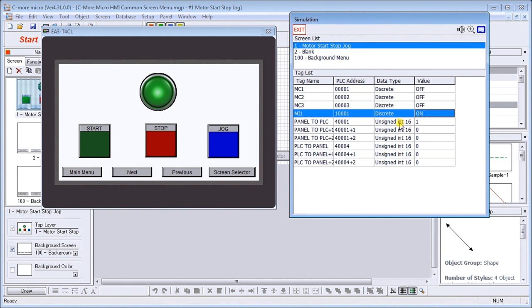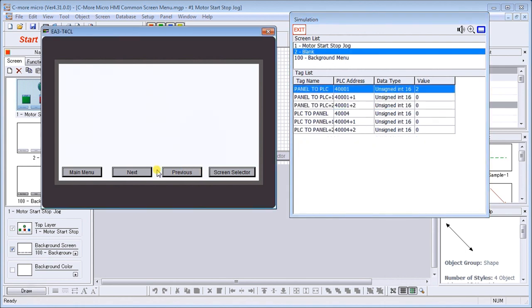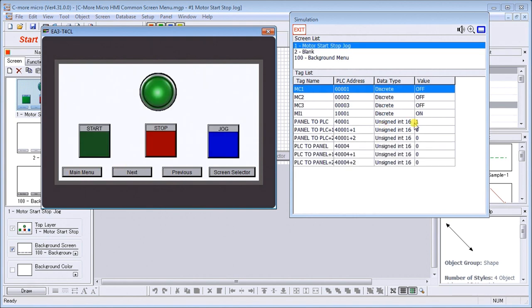I can also change pages here. You'll notice that this first one here, Modbus address 40,001, this is my panel to PLC. If I change pages, we'll hit previous, you'll see page number two then gets put in there. If I hit main menu again it gets back to page number one, so it's automatically updating as we modify on our simulator.